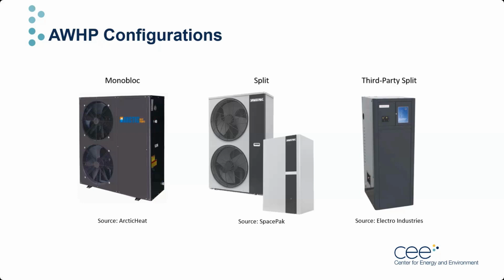In our market scanning effort, we shortlisted 47 systems that were potential candidates for field installations, 34 of which were monoblocks, which is the dominant configuration in the European market as well. A further 8 products were third-party split systems, and 5 were matched split units like the SpacePak system we see here. Additionally, 44 of the 47 were able to provide cooling in addition to heating, and 35 products explicitly note hot water integration as well.